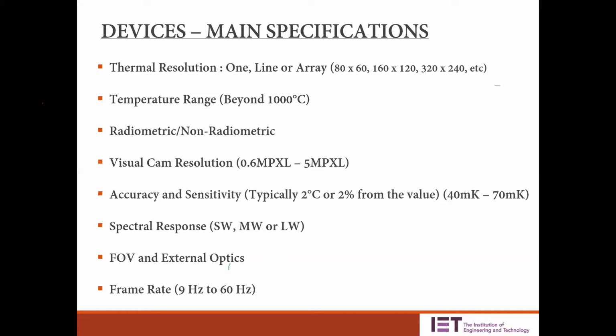screening. And the spectral response means that we spoke about the infrared spectrum being divided into 4: the short wave, the medium wave, the long wave, and the very long wave. And if you're buying an imager, depending on your application, you need to decide the spectral response, because most of the applications will lie in the long wave, which is from 7.5 microns to 14 microns. But there are certain very specific applications for short wave and medium wave. So be careful about it. And field of view will decide what you see. And the external optics will provide additional accuracy. We will be speaking about the FOV and the external optics in slides to come.